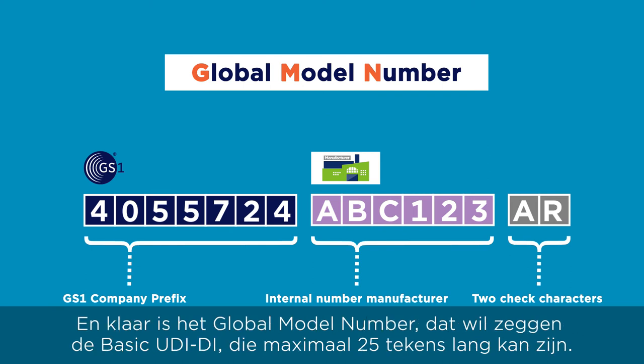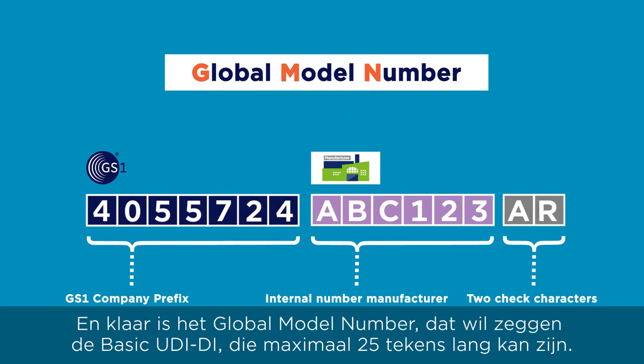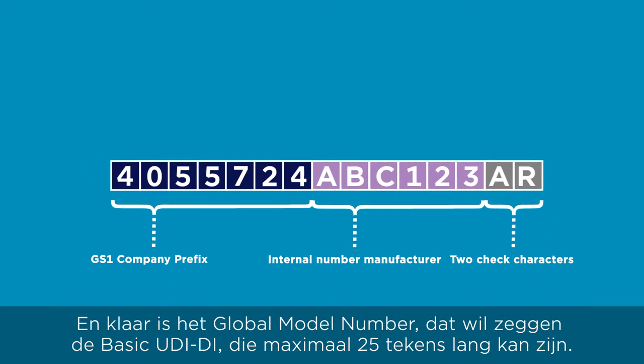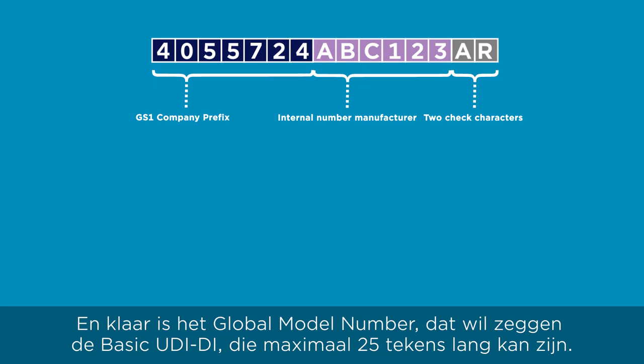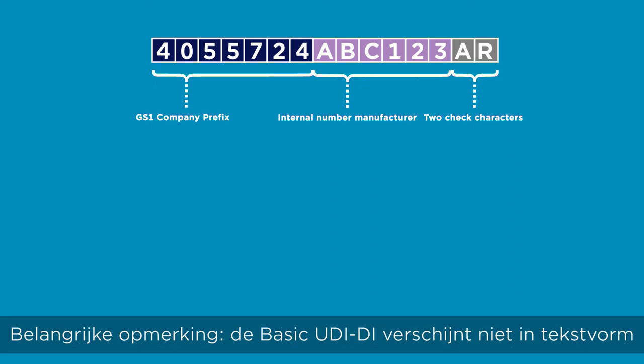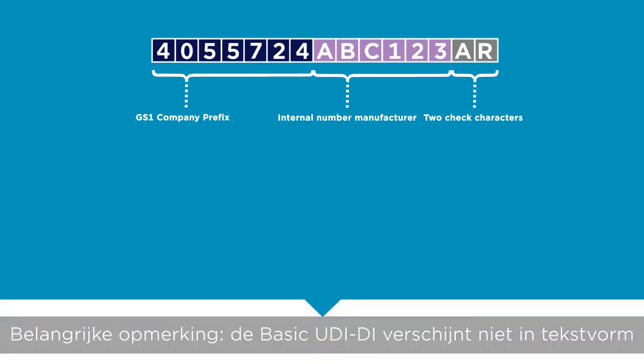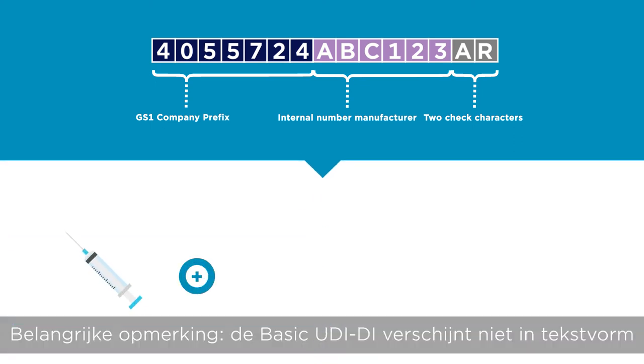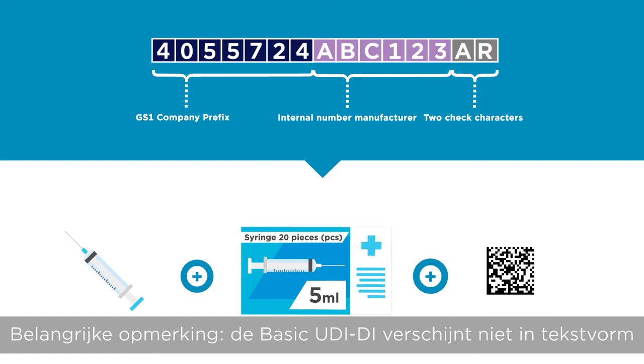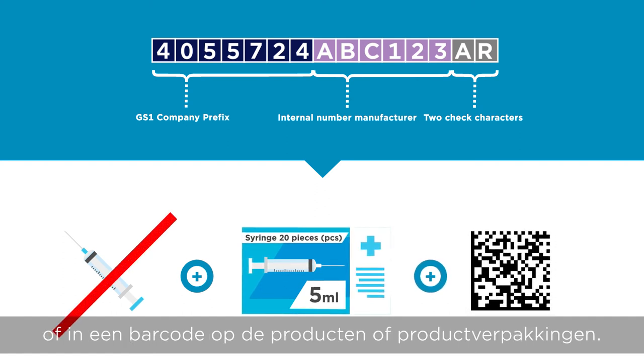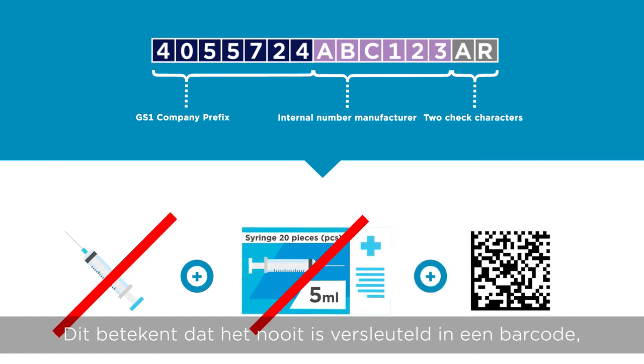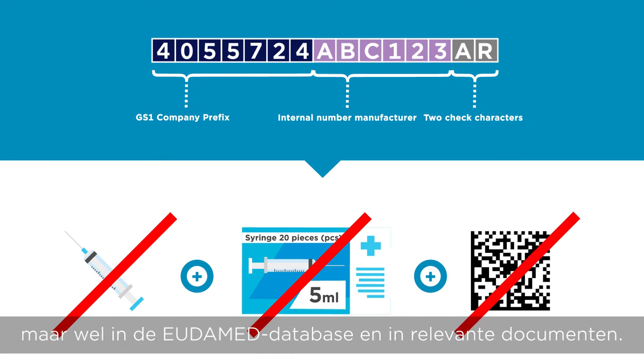The global model number — that is the basic UDI-DI — which can be up to 25 characters long, is ready. Important note: the basic UDI-DI does not appear in text form or in a barcode on the products or product packaging. This means that it has never been encoded in a barcode, but is used in the EUDAMED database and in relevant documents.